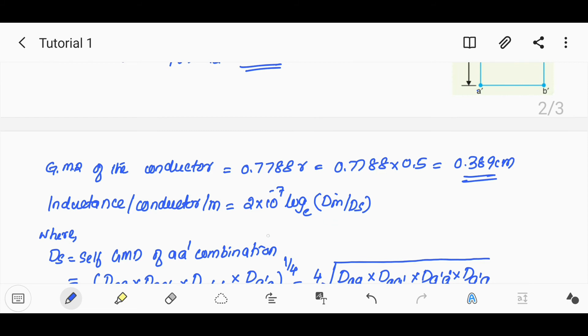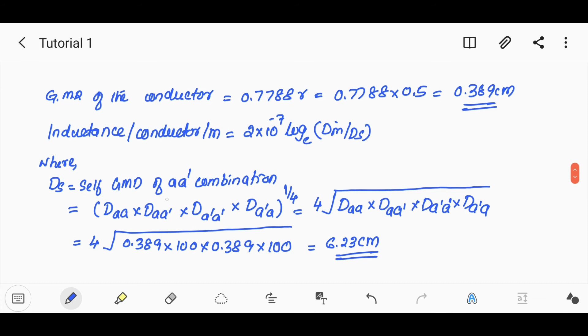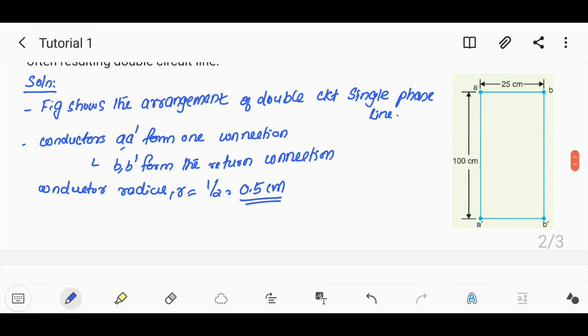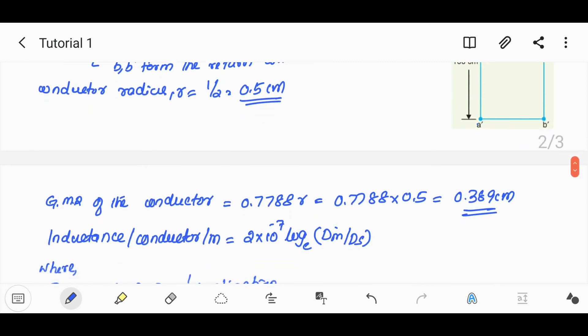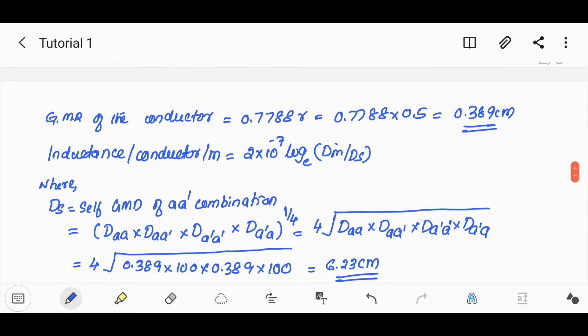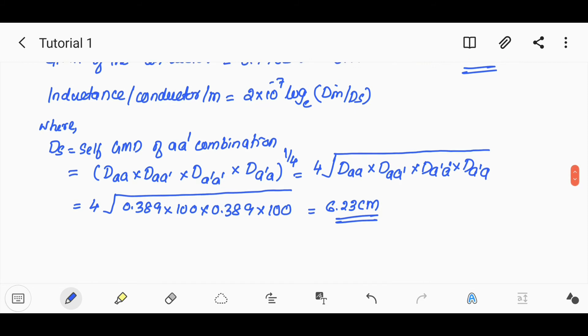We calculate the self-GMD: Ds = fourth root of (D_AA × D_AA' × D_A'A × D_A'A'). Here D_AA (the GMR of the conductor) is 0.7788 × r = 0.7788 × 0.5 = 0.389 cm. The spacing between A and A' is 100 cm.